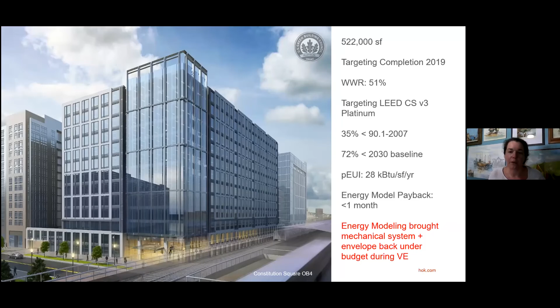Our engineering consultant said, hear me out - what if we went with slightly more expensive glass, but a little less of it? I think we're just on the edge of our peak cooling loads, enough that we could reduce the peak cooling load enough to get rid of a chiller. Our client said, walk out the door and do it right now. So we did - we upgraded the glass and reduced the window-to-wall ratio from 56 to 51%.